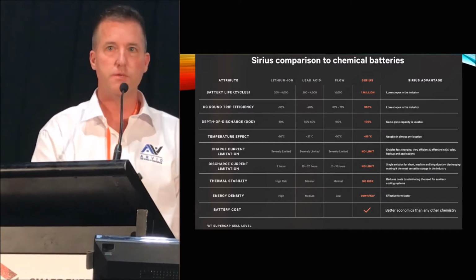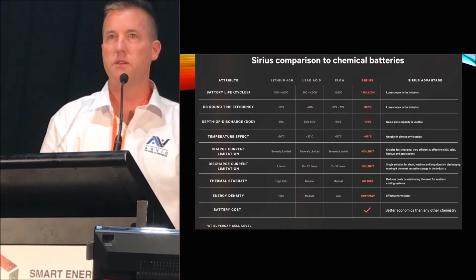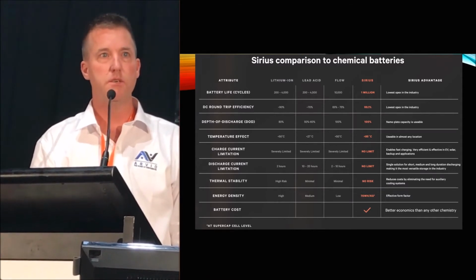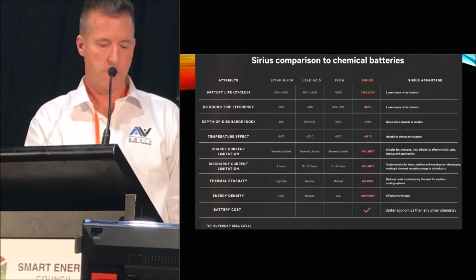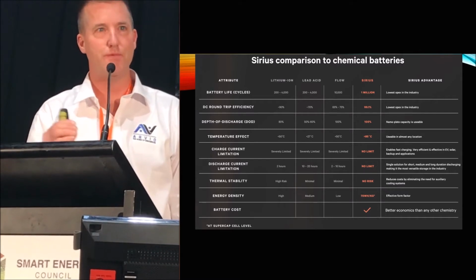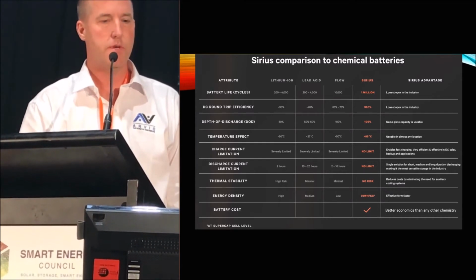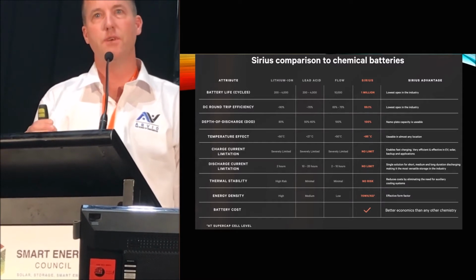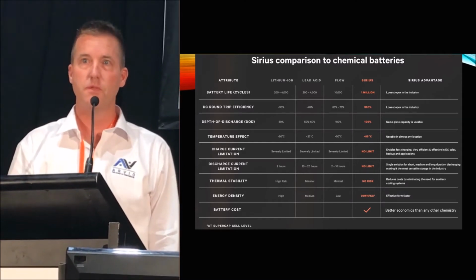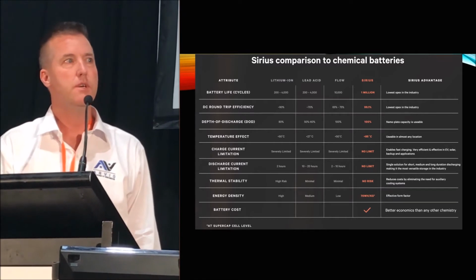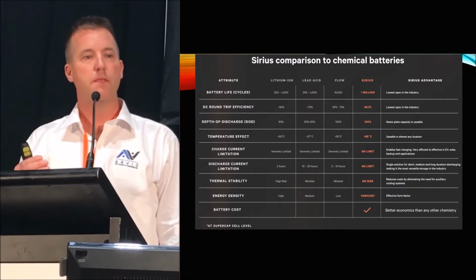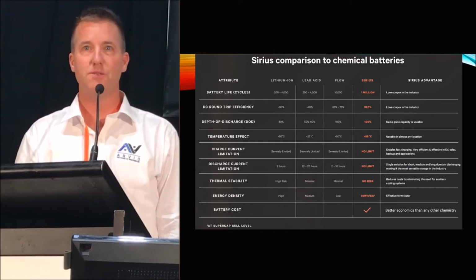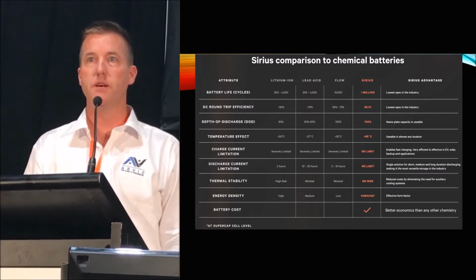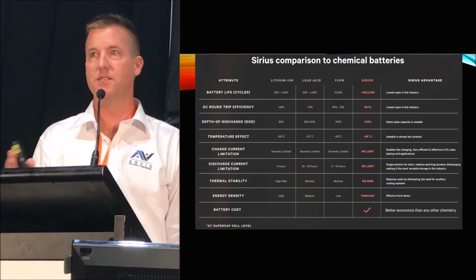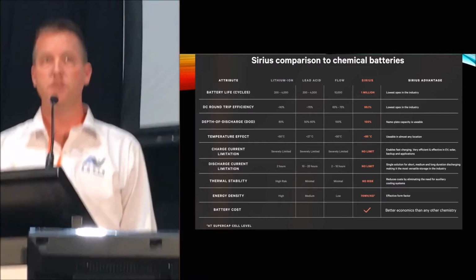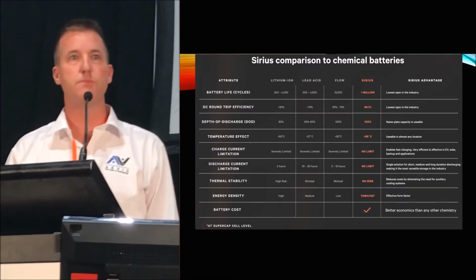That pack you saw before is a 3.55 kilowatt hour module, and it can peak at about 15 kilowatts DC before the circuit breaker trips. I've actually peaked it at about 23 kilowatts for short bursts, so it's very powerful. Typically, it's no longer the battery that's the limit, it's now the inverter, which is a great place to be from a design point of view. You don't design around peaking power anymore, you design around kilowatt hours. If you have a requirement for 10 kilowatt hours, it's a 3.5 kilowatt hour pack, you take 10 divided by 3.5 and you need 3 batteries, that's it. You don't have to think about peaking power or temperature or anything, you just put them in parallel.